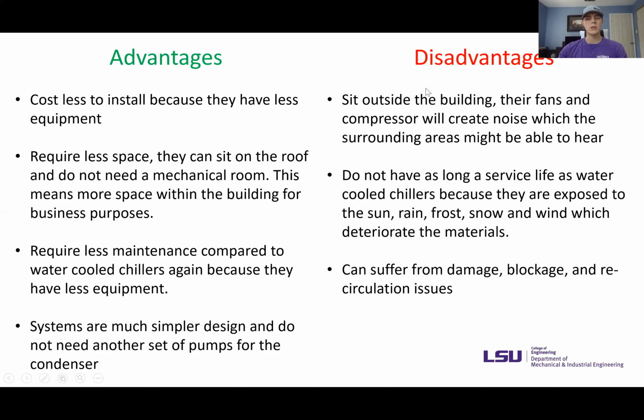So some of the disadvantages would be that the unit is always exposed to the environment. It sits outside, and their fans and compressors will create noise, which the surrounding areas might be able to hear. They don't have as long a service life as water cooled chillers do, because they're exposed to sun, rain, frost, snow, wind, and all those things deteriorate the materials on the unit. They can also suffer from damage, blockage, and recirculation issues. What that means is that the condenser fans, as they are dispersing the unwanted heat, if it's in a confined space that doesn't have good air circulation, it might pull that hot air back through the condenser and not work as efficiently.